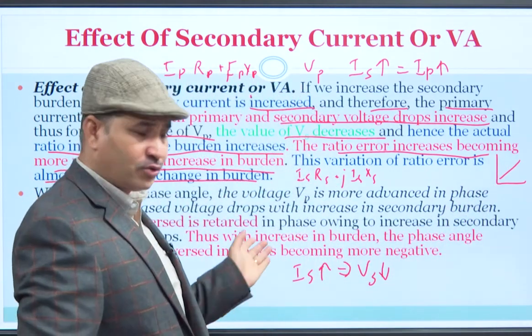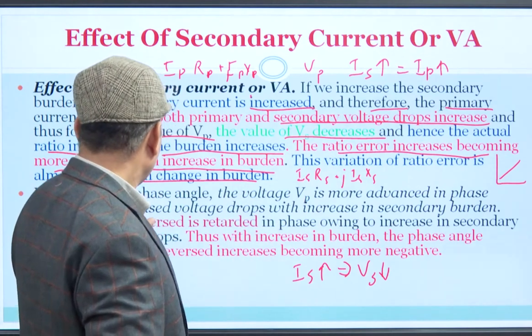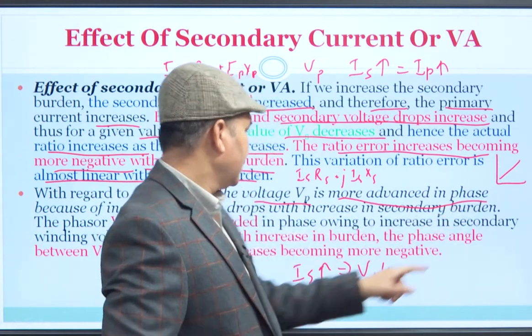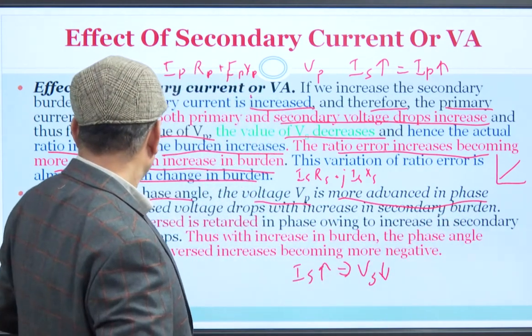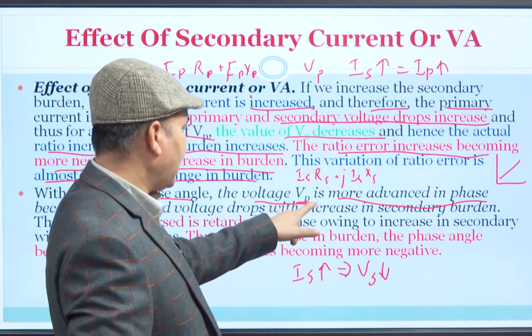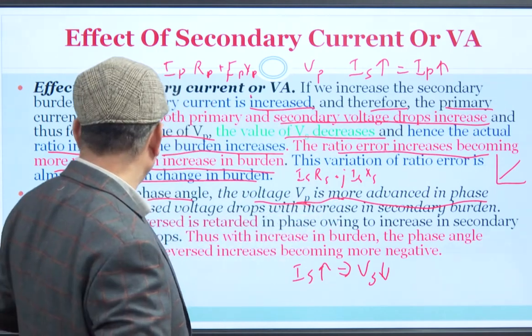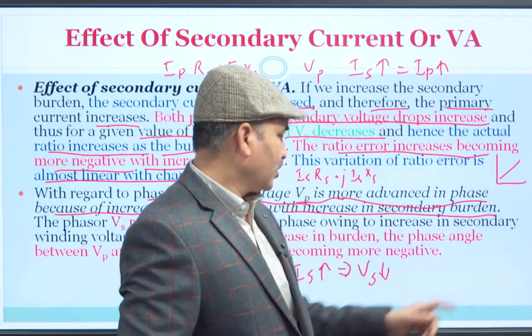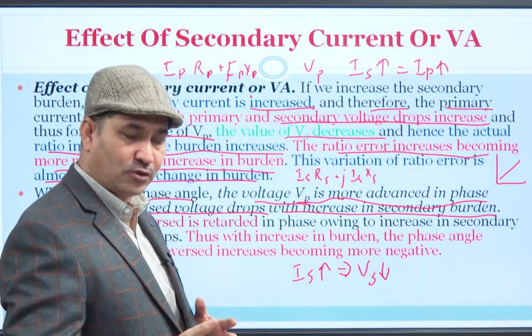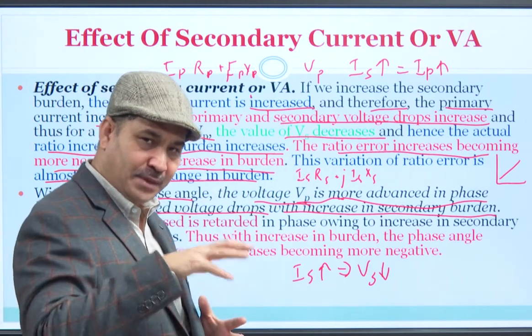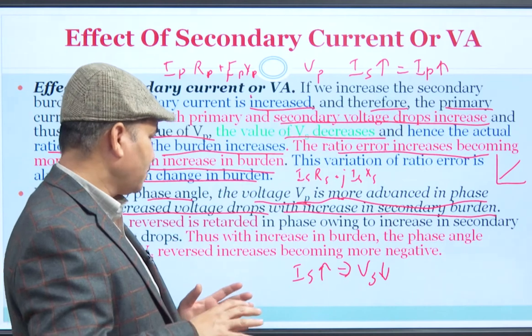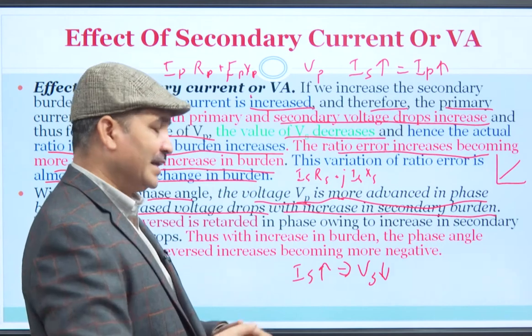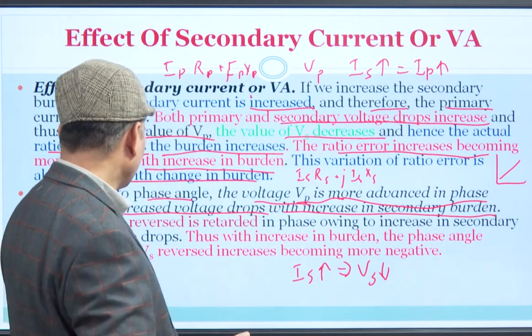With regard to the phase angle: Vp is more advanced in phase because of the increased voltage drops with the increase in secondary burden. Because as secondary burden increases, voltage drops increase and Vs decreases. When Vs is referred to the primary (i.e., Vs reversed), it is retarded — it lags. So the phase angle between Vp and reversed-Vs becomes more negative as burden increases, because Vp is ahead and reversed-Vs is further behind.